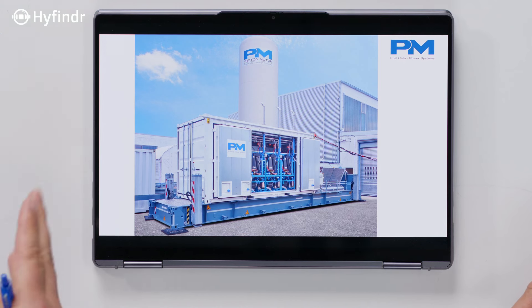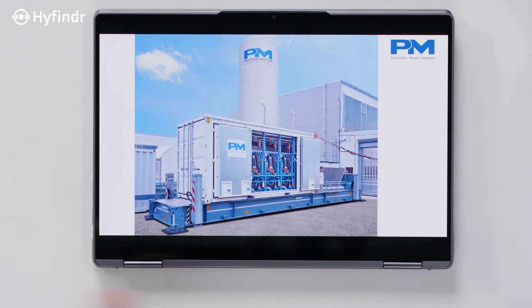To get a battery of that size is possible, but also big. With containerized hydrogen storage at 350 or 500 bar, or even a metal hydride storage system, it's much smaller than the fuel system. You have to look at what is the right hydrogen storage solution. The more hydrogen you have, the longer this could run. You can also do a swapping of the hydrogen storage system, which is not possible with batteries — if the battery is empty, you cannot swap anything. With a logistic concept, you can extend the runtime indefinitely.